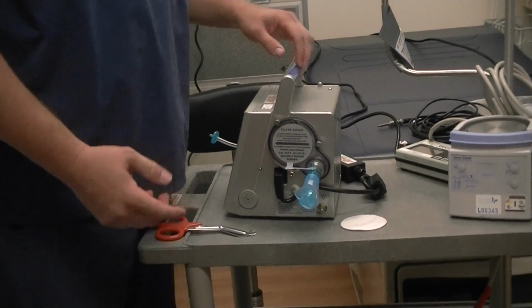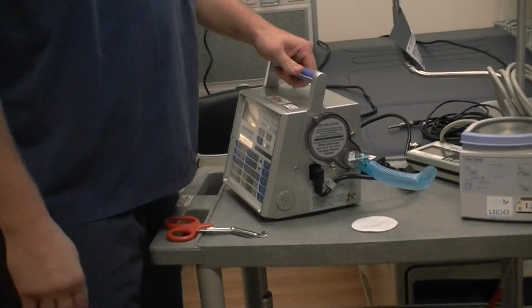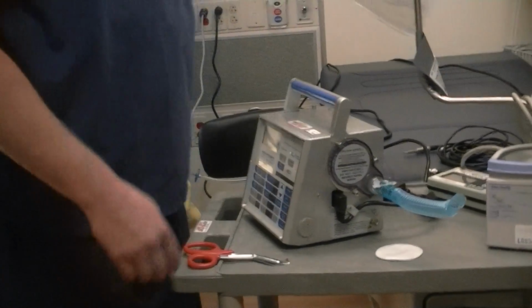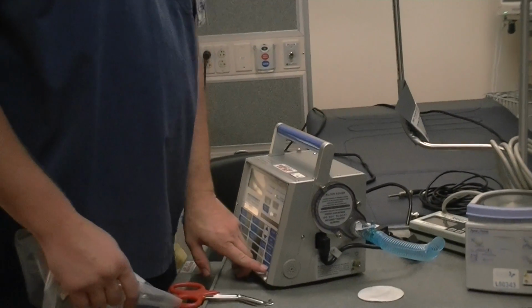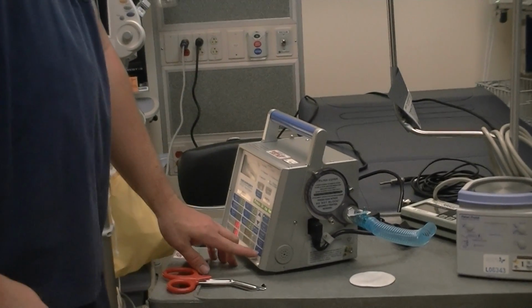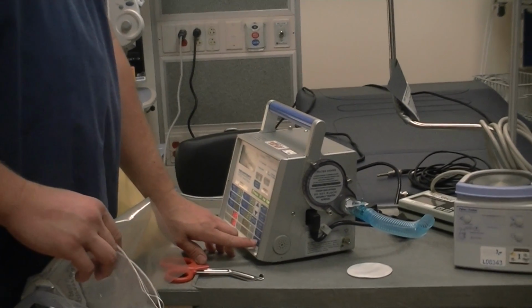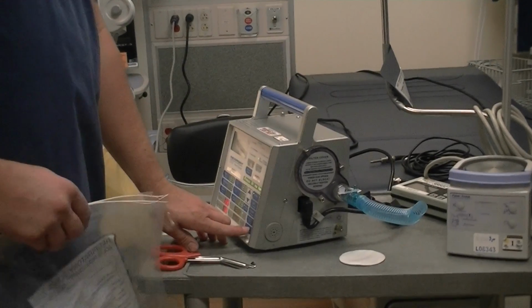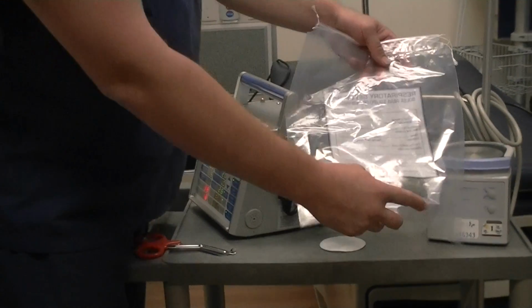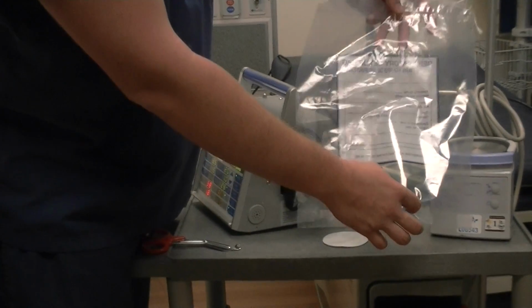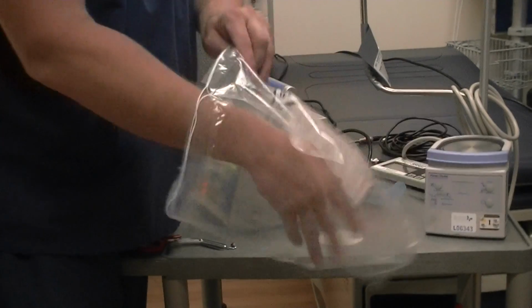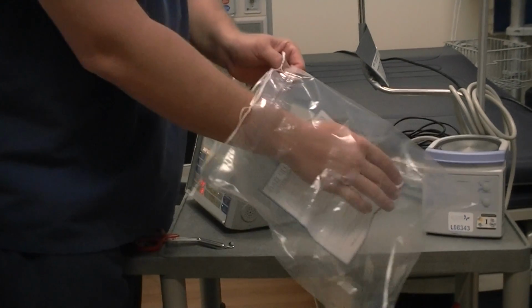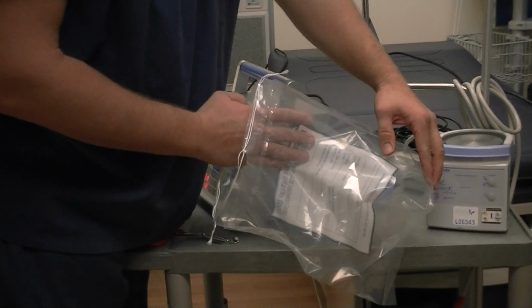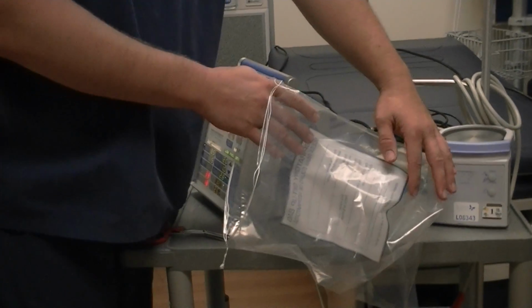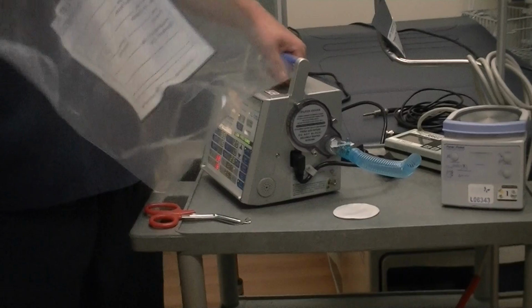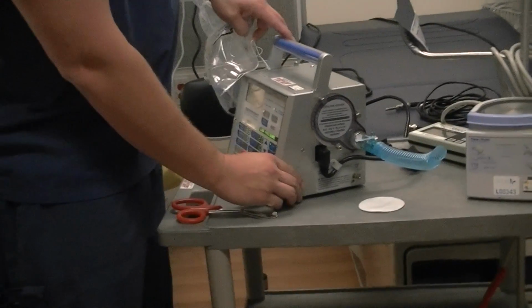Now, one recommendation I do have that I think everybody should get in the habit of doing is, I'm going to turn on the ventilator here real quick. Since we have a lot of bags hanging down in the general area of the ventilator, what tends to happen is the bags will get sucked in. The bags will get sucked into the ventilator. Basically, your ventilator will not suck in any more air because your bags are polluting the airway.